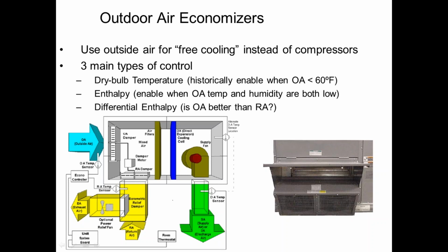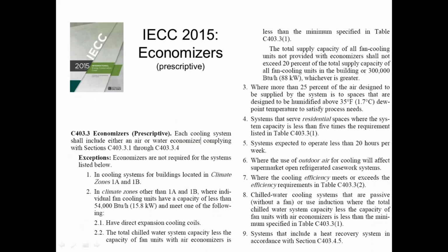You could also do enthalpy, which is essentially, from a layman's standpoint, looking at temperature and humidity. And if both of them are good, then I'll go ahead and use my economizer instead of compression. And then one step better than that is differential enthalpy. So I don't care how warm it is outside or what specific number, right? I just care, is the outdoor air cooler and drier than the return air? Because my air can only come from one of 2 paths. It comes from the outside or it comes back from the space. So whichever one is cooler and drier, hence lower enthalpy, I'm going to use that one, right? So that's the basic economizer discussion.